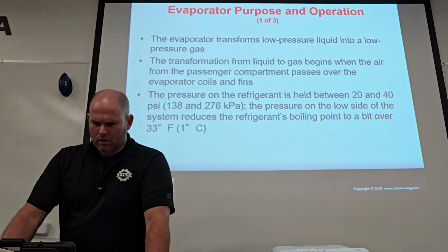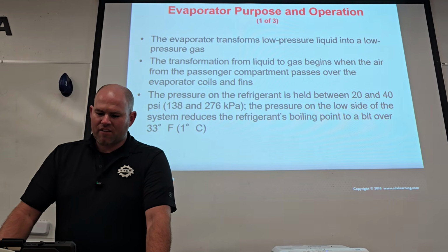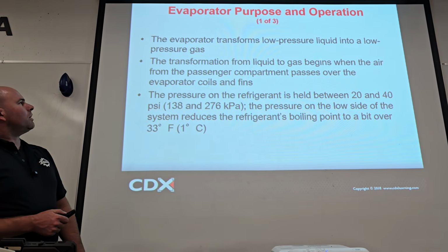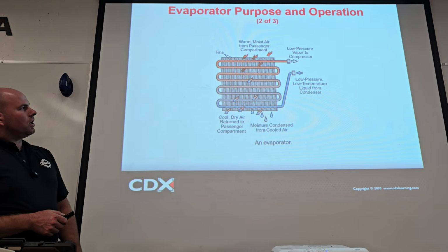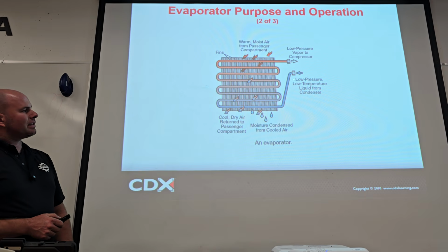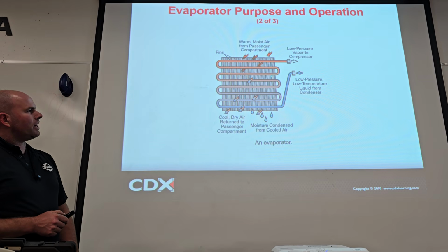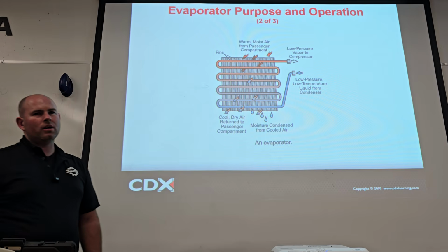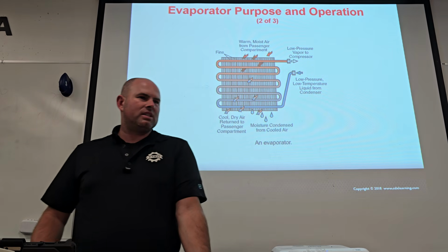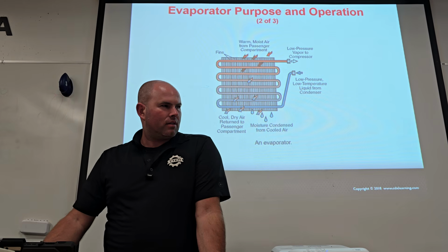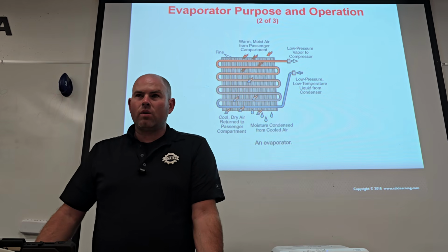Cool. And then, like I was saying, when we get into the evaporator, remember it's gonna do liquid into a gas. So it's low pressure liquid. It's gonna bring in, and this is gonna basically boil it off, evaporate it, if you will, and it's gonna leave. Actually, it may leave slightly warmer, but it's probably not gonna be sensible heat. What would it be? What would that change of state have been? Latent heat.